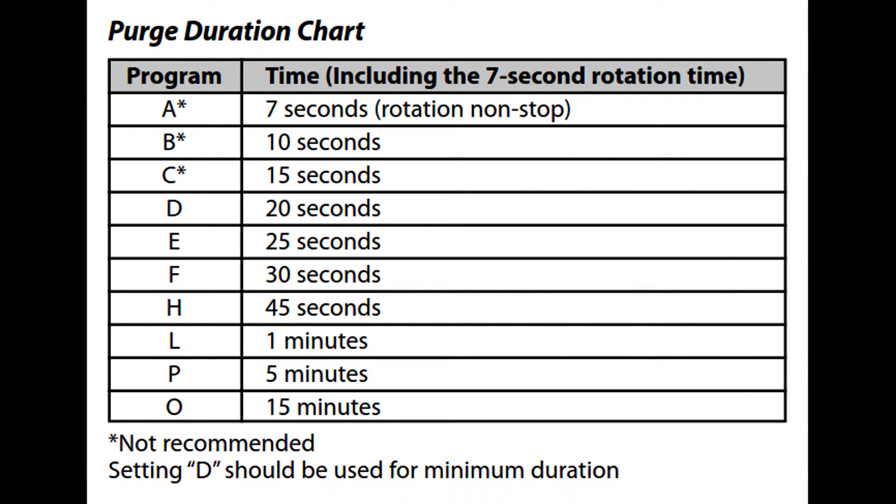Here is the chart of pre-programmed options that the purge duration can be set to. Settings A, B, and C are not recommended for use because of their short lengths. Setting D, or 20 seconds, is the shortest recommended purge duration.